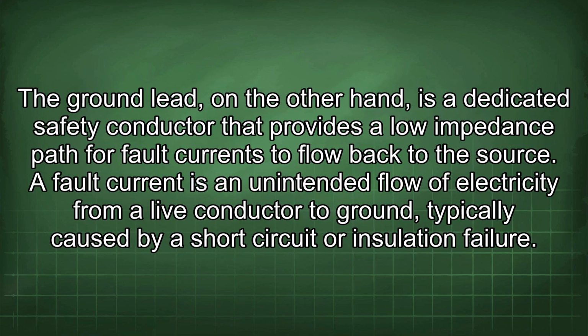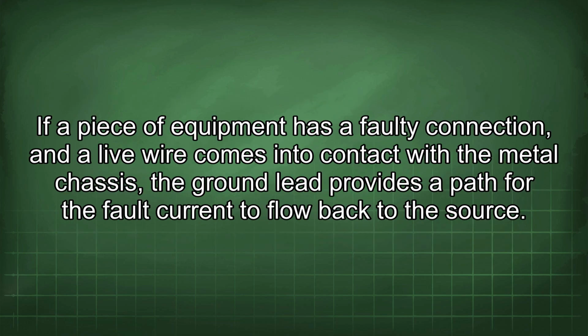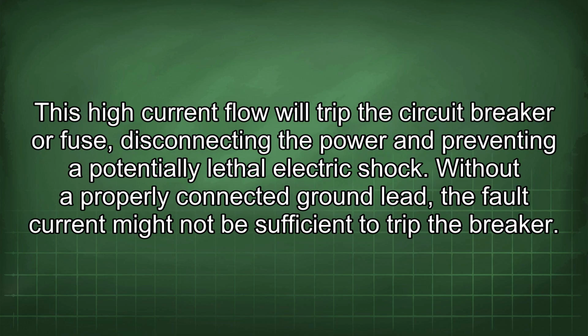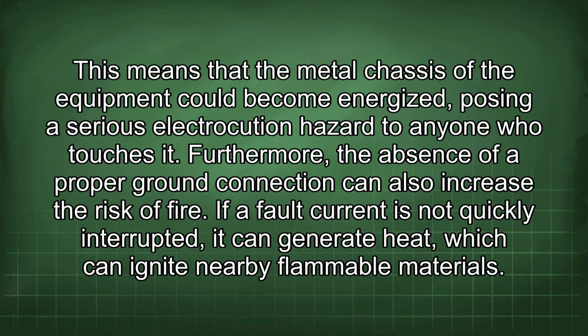The ground lead, on the other hand, is a dedicated safety conductor that provides a low impedance path for fault currents to flow back to the source. A fault current is an unintended flow of electricity from a live conductor to ground, typically caused by a short circuit or insulation failure. If a piece of equipment has a faulty connection, and a live wire comes into contact with the metal chassis, the ground lead provides a path for the fault current to flow back to the source. This high current flow will trip the circuit breaker or fuse, disconnecting the power and preventing a potentially lethal electric shock. Without a properly connected ground lead, the fault current might not be sufficient to trip the breaker. This means that the metal chassis of the equipment could become energized, posing a serious electrocution hazard to anyone who touches it. Furthermore, the absence of a proper ground connection can also increase the risk of fire. If a fault current is not quickly interrupted, it can generate heat, which can ignite nearby flammable materials.